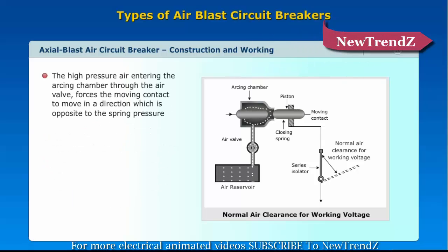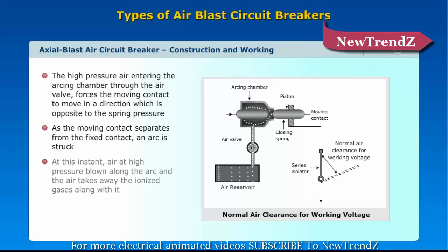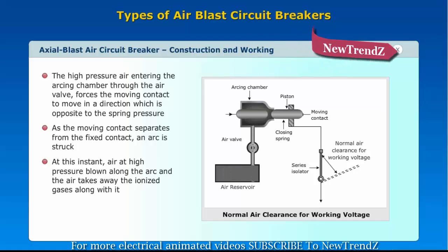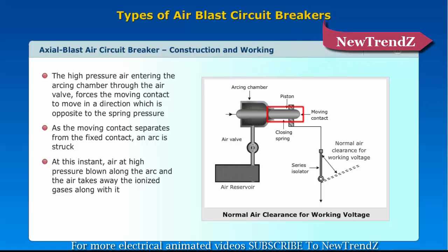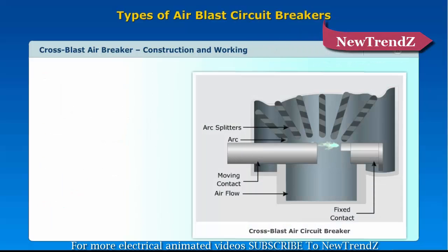The high pressure air entering the arcing chamber through the air valve forces the moving contact to move in a direction opposite to the spring pressure. As the moving contact separates from the fixed contact, an arc is struck. At this instant, air at high pressure is blown along the arc, and the air takes away the ionized gases along with it. Consequently, the arc extinguishes and current ceases to flow.